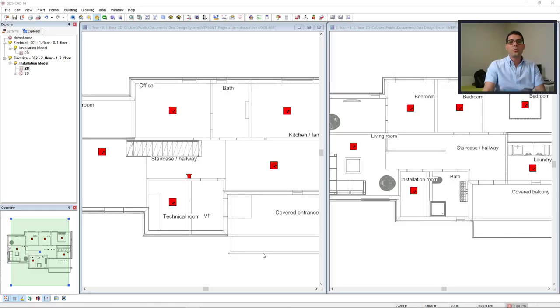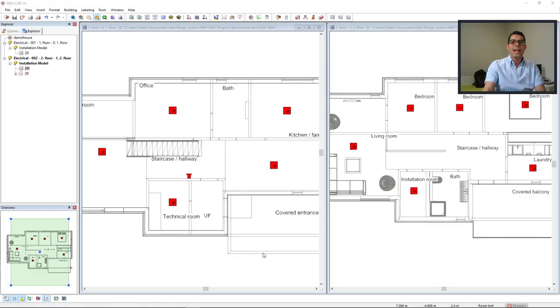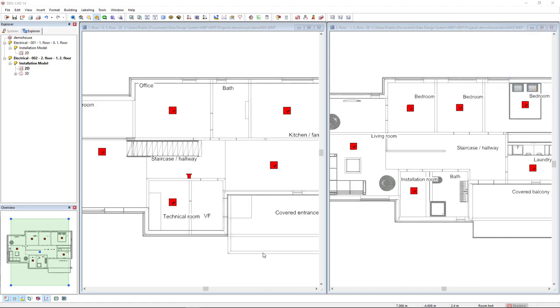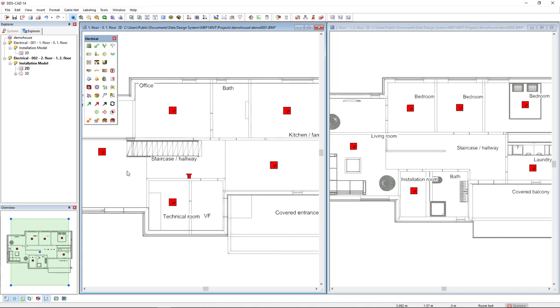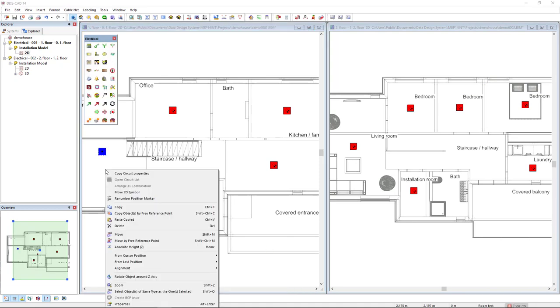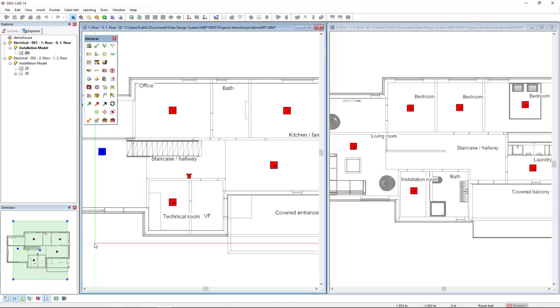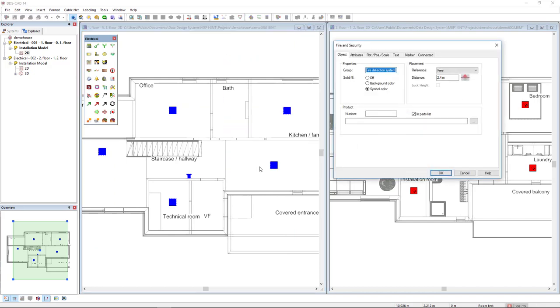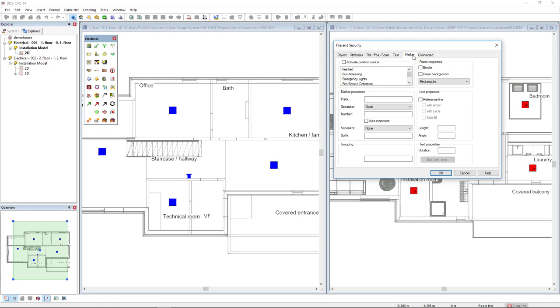First of all, I want to tag all these smoke detectors in the correct loop and sequence number. To do so, I will select all the objects from the first floor and access the properties. From the properties, I will select the tab marker. In the marker, I will activate position marker and select the predefined option fire smoke detectors.